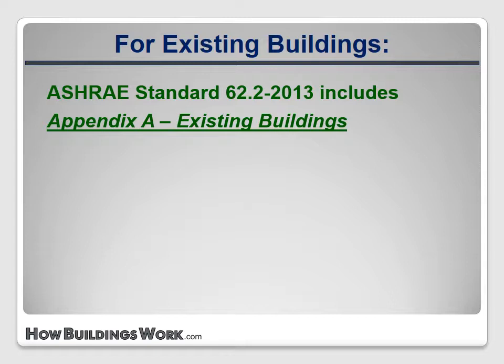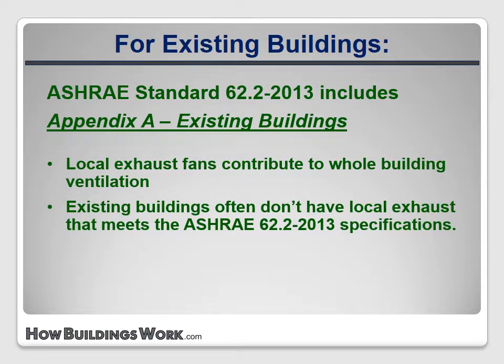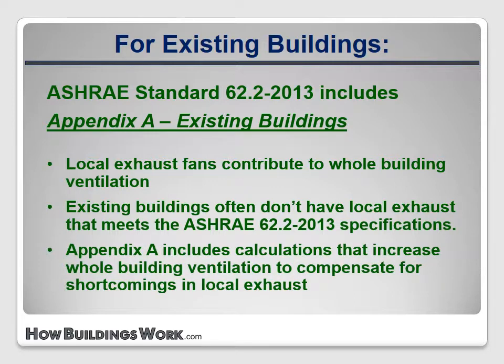The main changes relate to exhaust ventilation. Local exhaust fans like range hoods and bath fans contribute to whole building ventilation. The new construction calculations assume that those fans are in place and functioning properly, but existing buildings often don't have local exhaust that meets the specifications in ASHRAE 62.2. Appendix A includes calculations that increase the size of required mechanical ventilation fans to compensate for any shortcomings in the local exhaust systems.